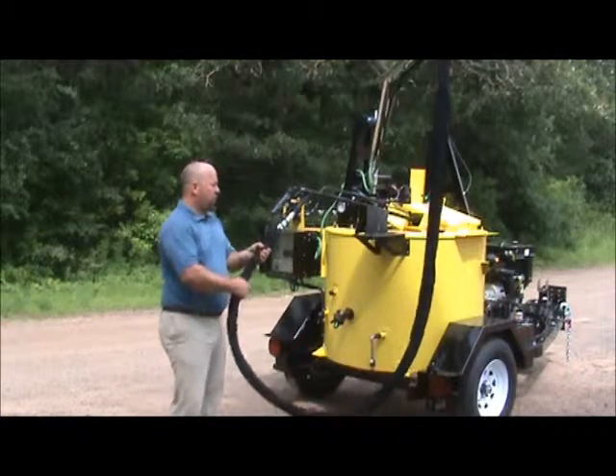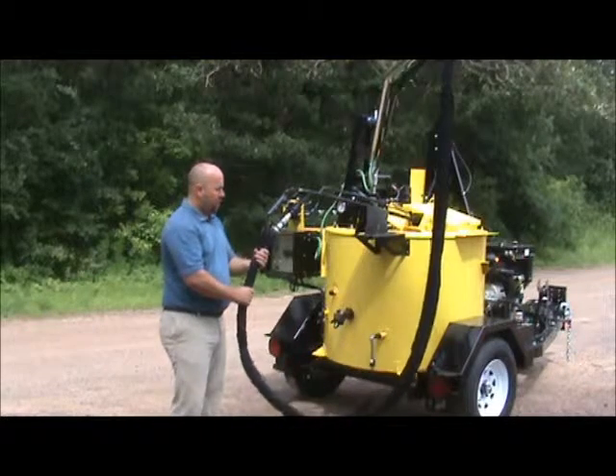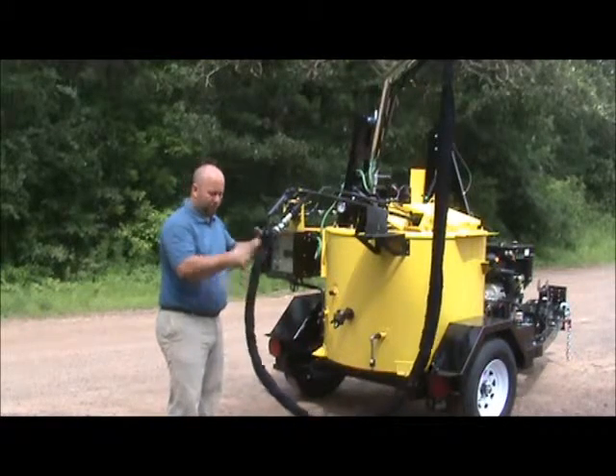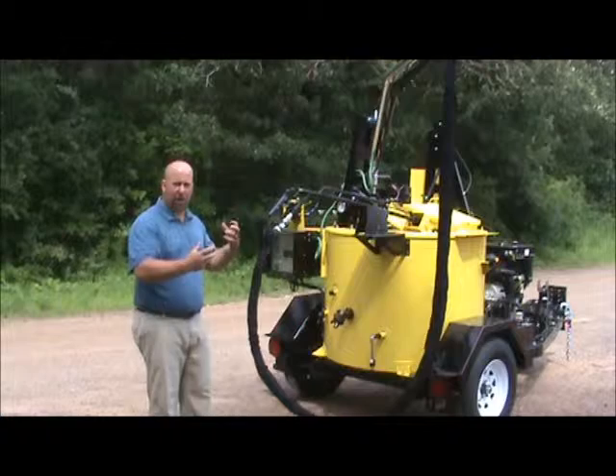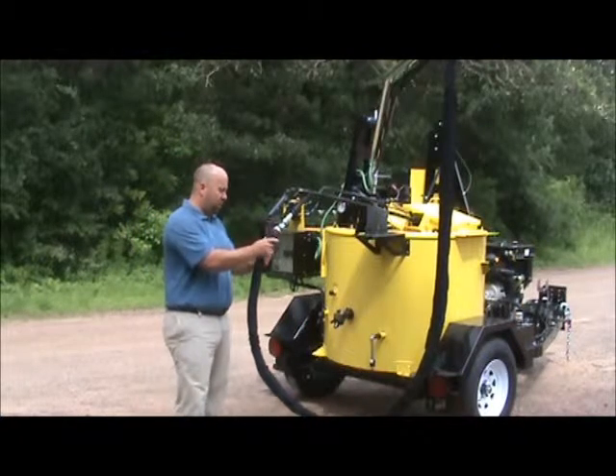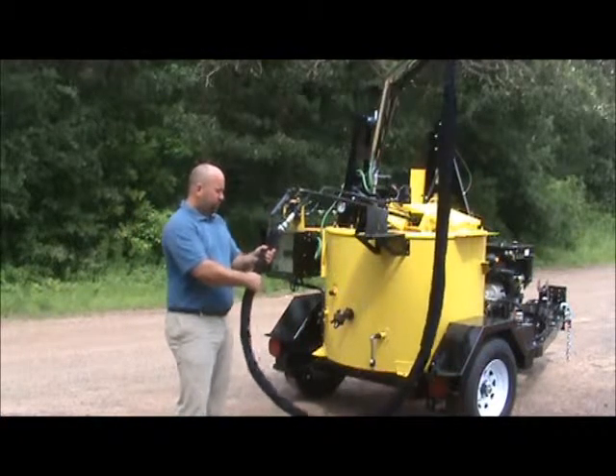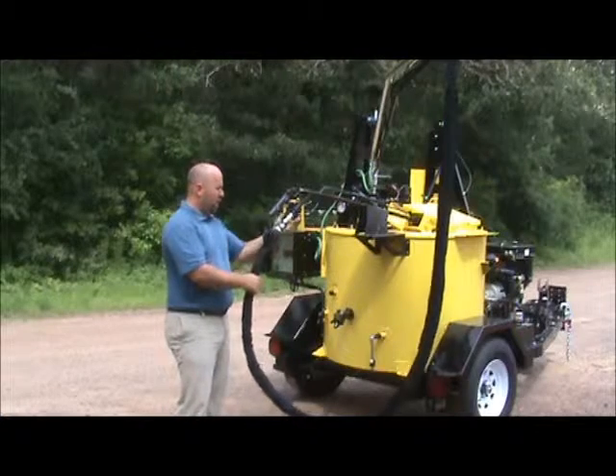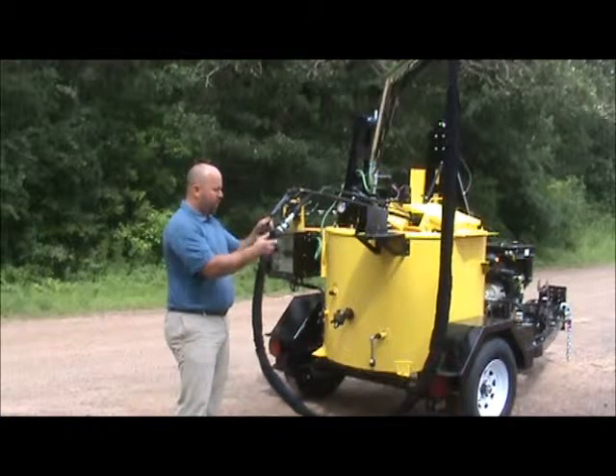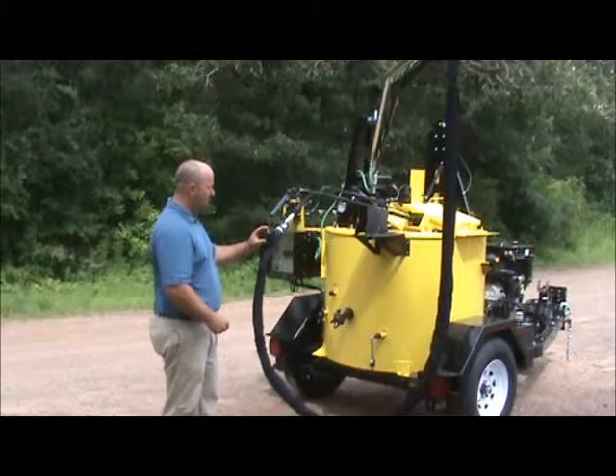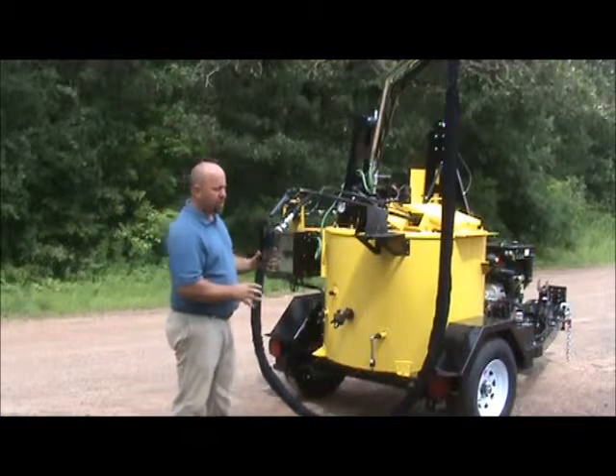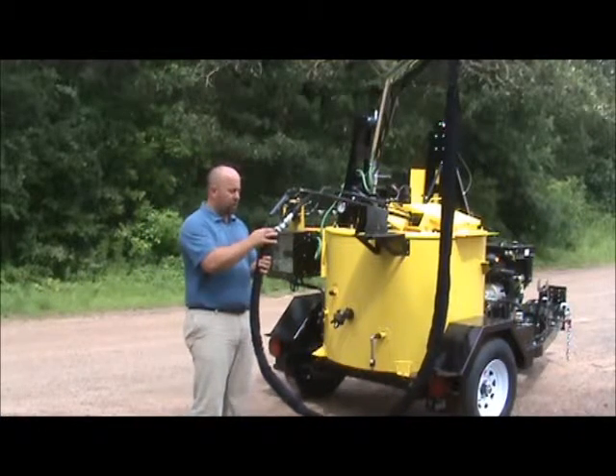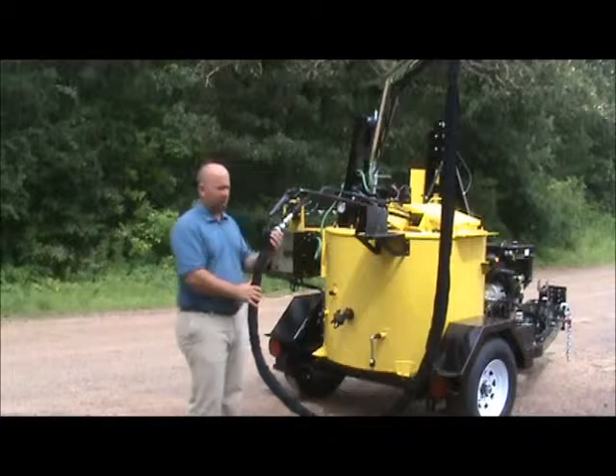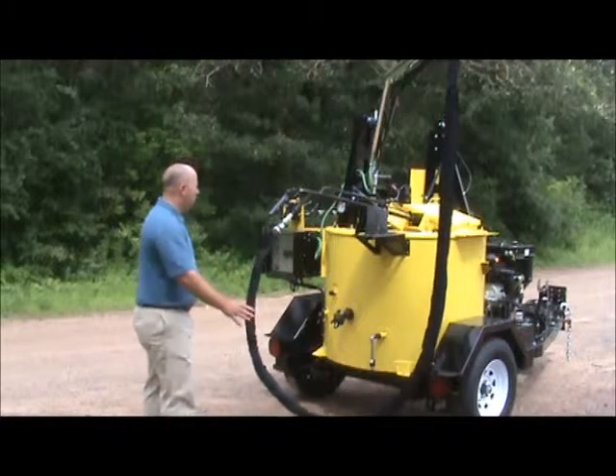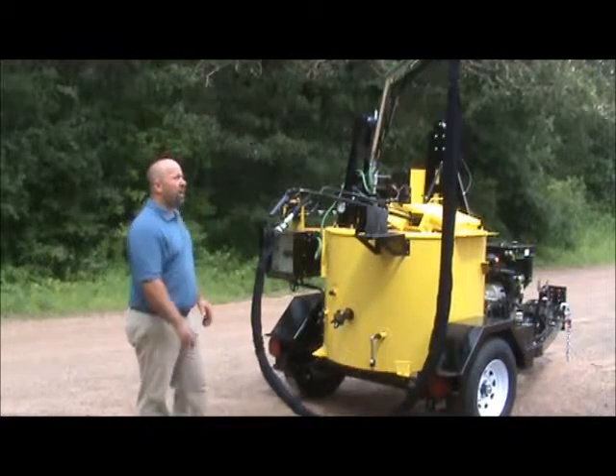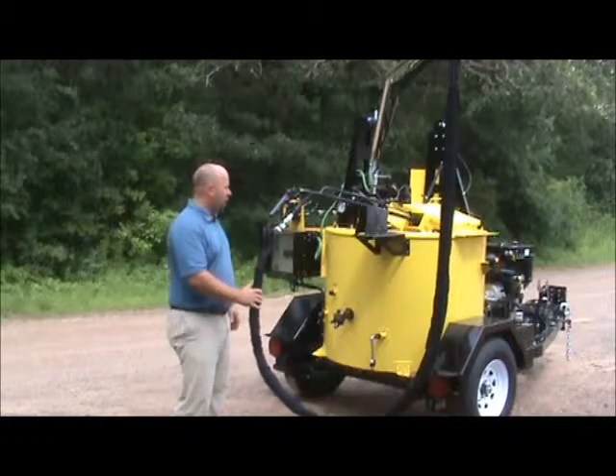Now, you have a swivel between the wand and hose. You just have to be careful that if you set the hose on the ground, the next guy picks it up, he doesn't twist the wires up on the hose. The hose is always going to swivel, but you want to make sure that we don't wrap these up tight and pull the plugs apart. All of the wiring on our system is a soldered connection, or it's a weather pack type connection, like what you're seeing here on the wand and hose. So that's kind of your basic operations of the heated hose system.